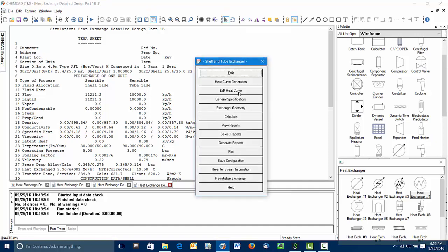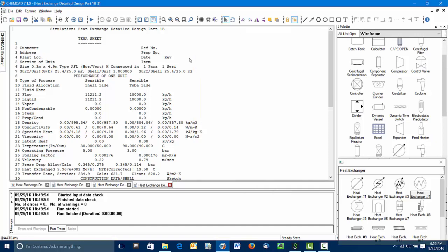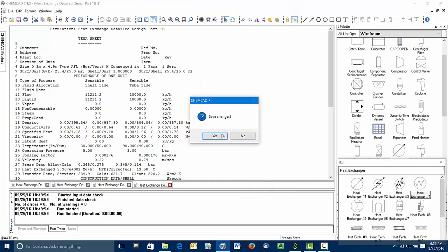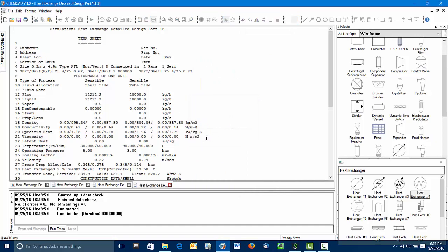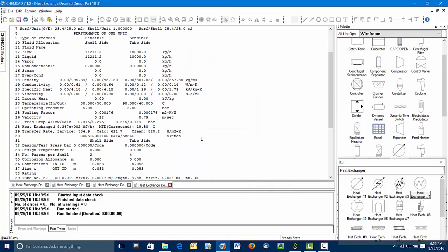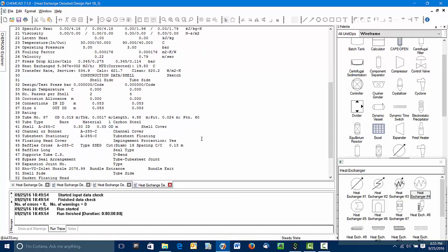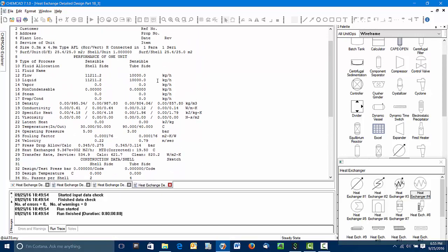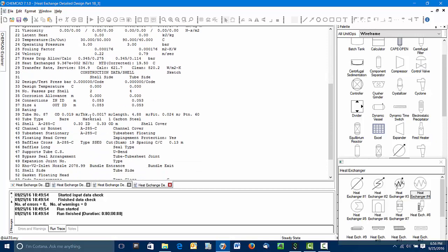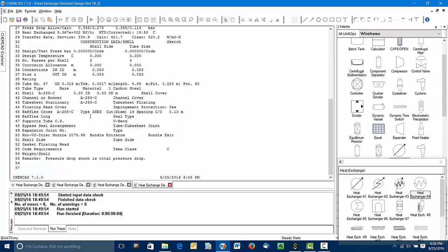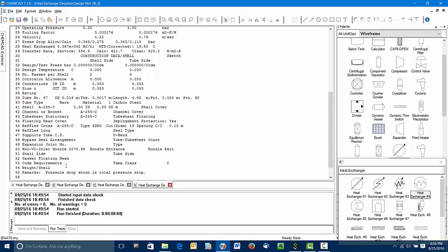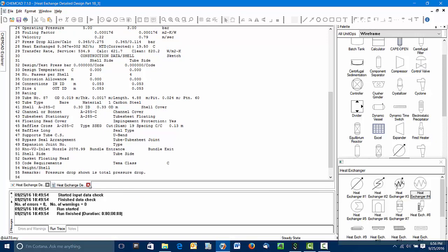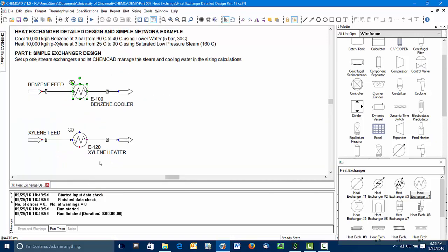Let me exit out of here. We'll save these changes. Actually, one thing I'll say about the TEMA sheet is in addition to some of the basic design parameters here, it also provides things like the sizes of the nozzles coming in. Here you can see the inlet ID for the shell side, the inlet ID for the tube side, and same for the exit. This lets us know physically how big these nozzles are going to need to be. So let me close this out. ChemCAD has saved this information.